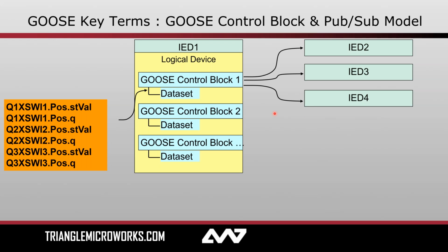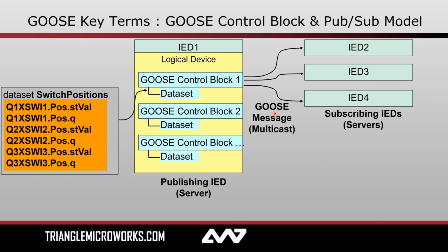So another key difference here that I want to point out is that I no longer have the restriction of having a single server subscribing to a single control block like I had in client-server communications. GOOSE is multicast, meaning unless I do something to change that, it will be received everywhere by everyone. When I say received, I just mean that it will make it to the Ethernet interface on these devices. It doesn't mean that these devices will be configured to subscribe to them, but it is sent out everywhere on the network.